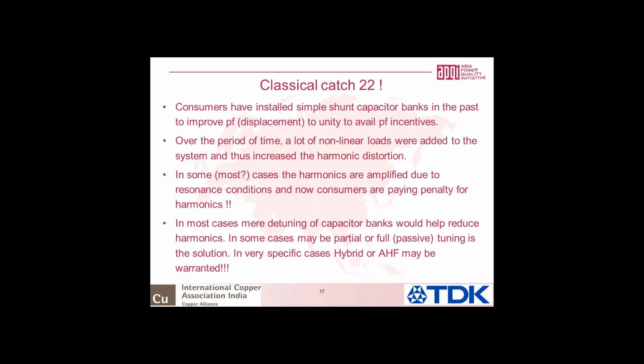But over a period of time, the entire network got distorted, because in the last 10, 15 years a good portion of the loads we have been adding are nonlinear loads. Switched mode power supplies. Nobody uses a linear power supply. UPS, inverters, even the fan regulators today are solid state. Dimmerstats, light dimmers, LED bulbs. Even air conditioners today are inverter driven. So the amount of nonlinear loads is going up, which means the total distortion in the system goes up.